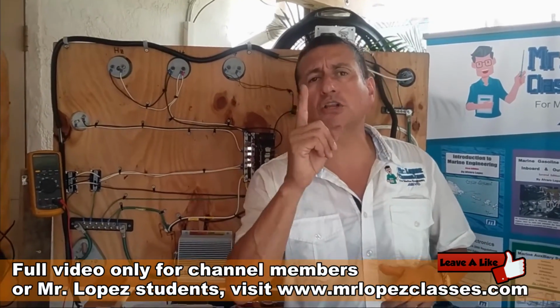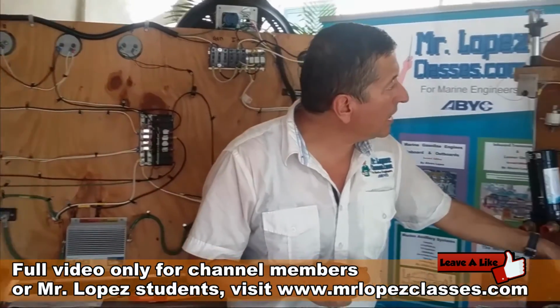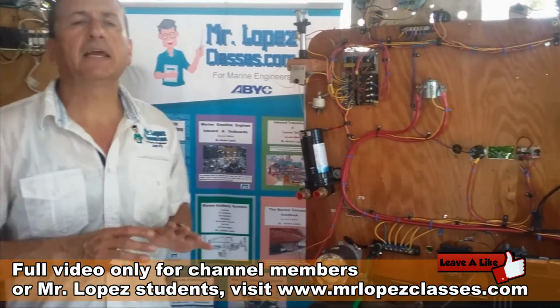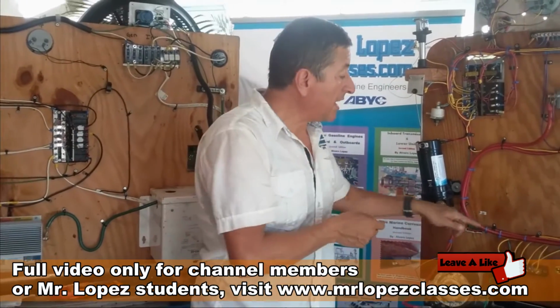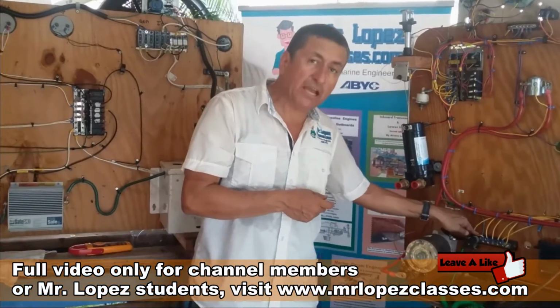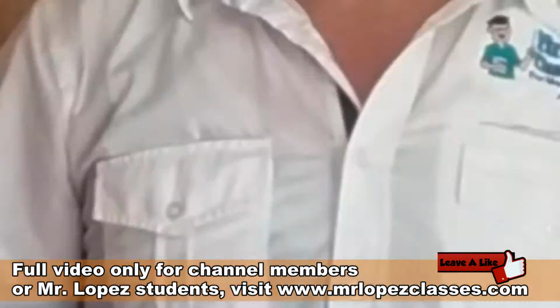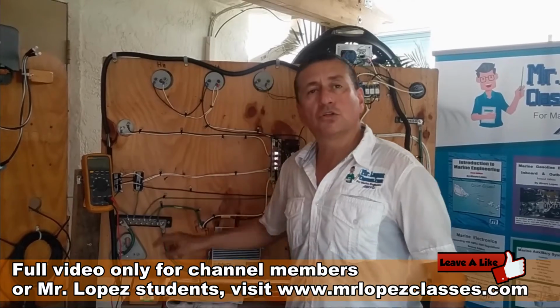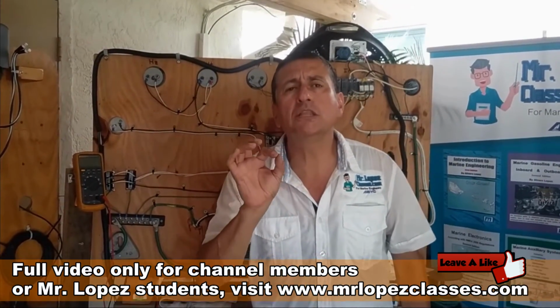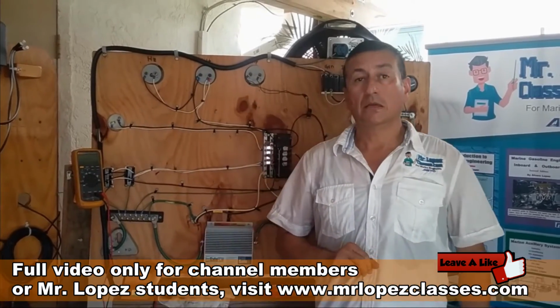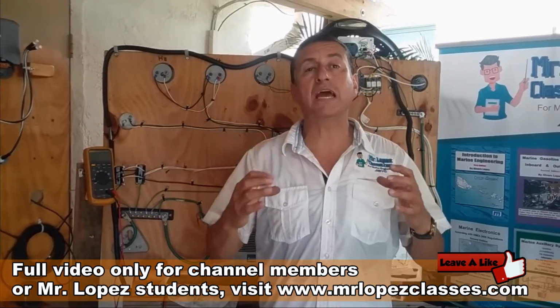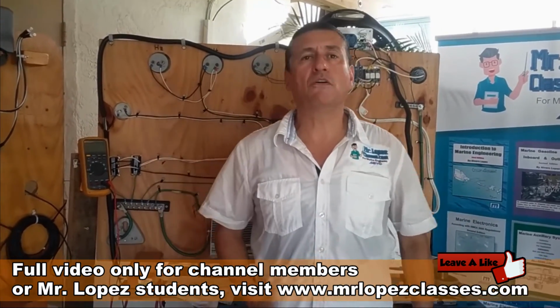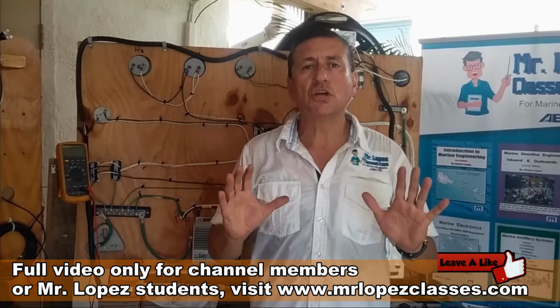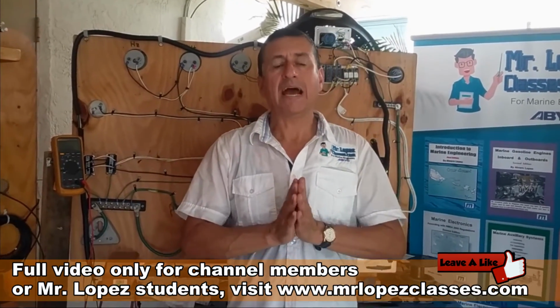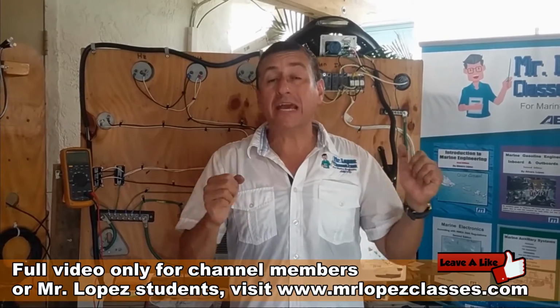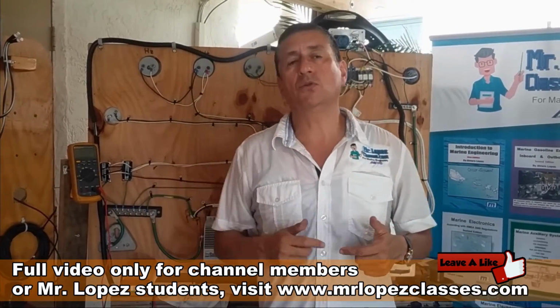In DC, I have more than one negative bus bar. I have one here, I have another one here, I have another one over there. All of them shall be connected together with the main negative bus bar, and the main negative bus bar connected with the bonding conductor. In normal conditions, through the bonding conductor, you have small DC currents draining. In an emergency, the bonding conductor is designed to drain big amounts of AC or DC current. That's the function of the grounding system. And this is the secret: keep everything connected to the bonding conductor and finally into the sink.